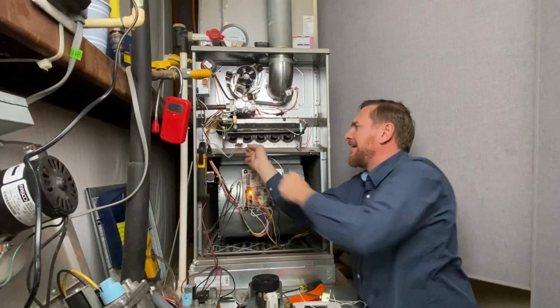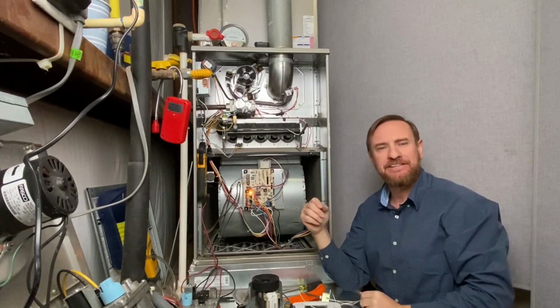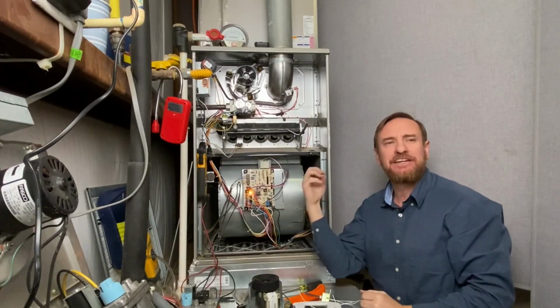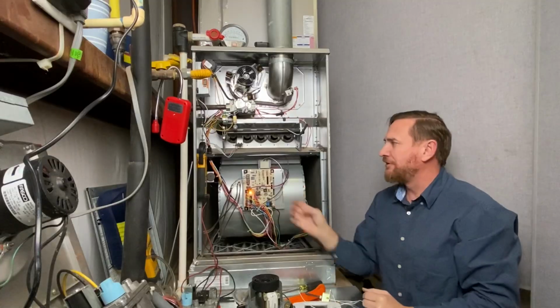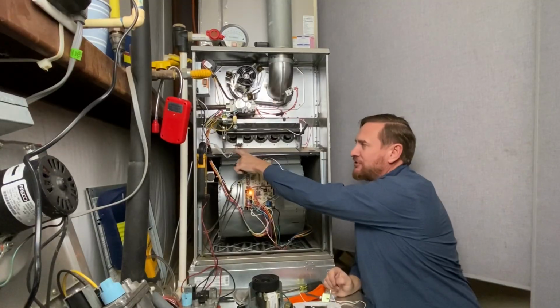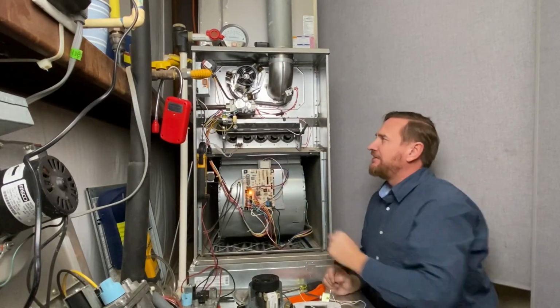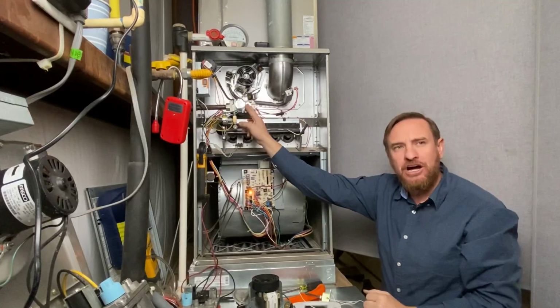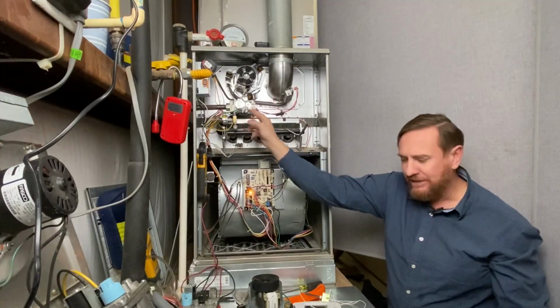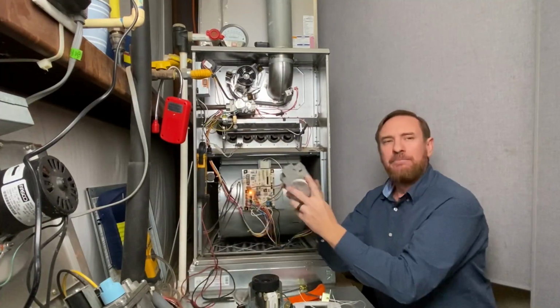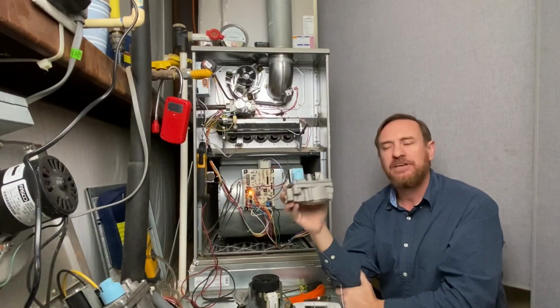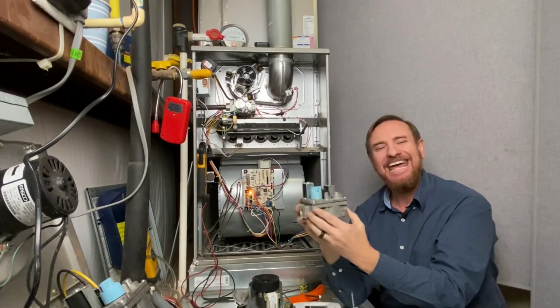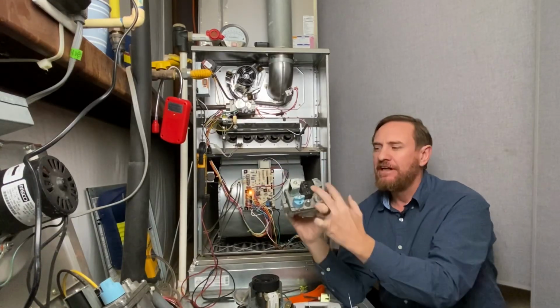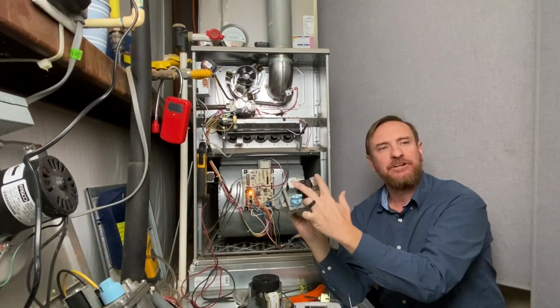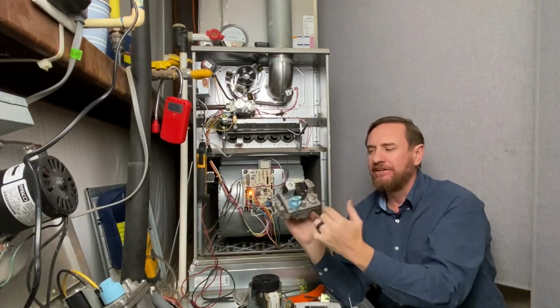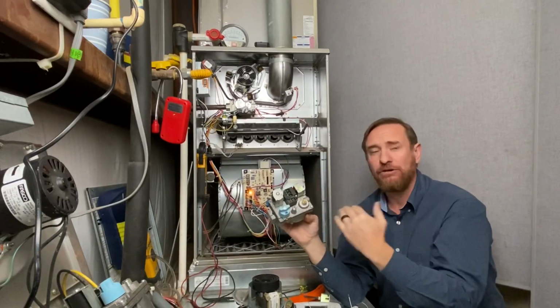So now that we've got this heating up, it's not going to heat up instantly. It's going to take a little bit of time for it to get to its optimum temperature. That's why there's a delay. Once it energizes this to come on, the IFC then energizes 24 volts to our combination gas valve. Now it's real important that I use the word combination gas valve because it's a combination of 2 parts, a pressure regulator and also a solenoid valve. This one has 2 valves, most of them do. It's called a redundant valve. They're in series to make sure that when it shuts off, it really shuts it off.